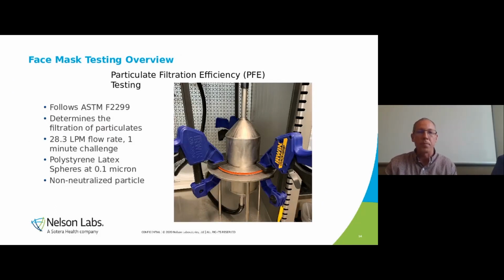All right, the next test is a particle filtration efficiency. So this is different than our BFE. This uses a non-viable particle. It's a polystyrene latex sphere. The standard requires a 0.1 micron. And this test is only required here in the US by ASTM F2100 and by the FDA. Europe does not require this test. But the FDA feels that it is important that we test submicron particles as well.